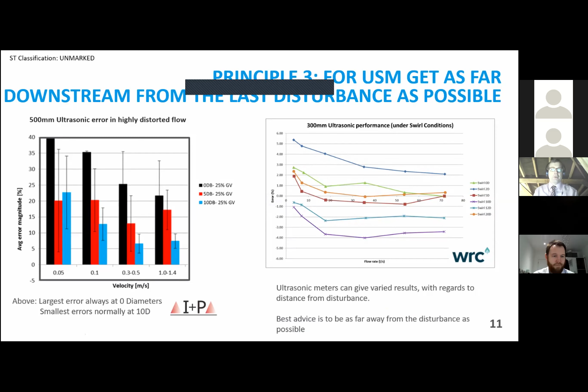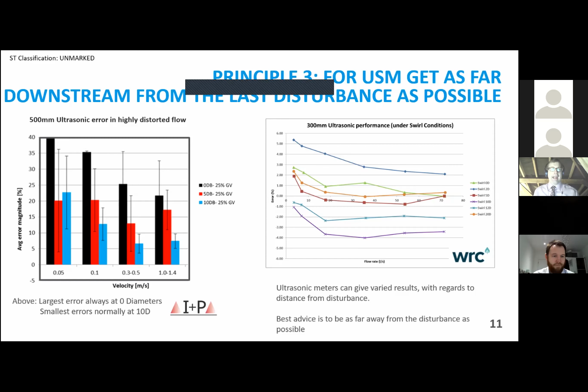But having looked at the results, and having looked at many results over the years, and having spoken to quite a number of my peers and those who are experienced in metering, our view is, with the game of probabilities, the best thing you can do in all likelihood to reduce errors on ultrasonic clamp-on meters is to try to get that meter as far away from the disturbance, whether it be 10 diameters or 20 diameters or 30 diameters or 50 diameters. Try to get it as far away from the disturbance as you can.